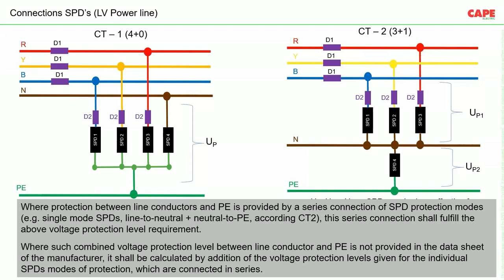A manufacturer should mention a combined voltage protection level in their datasheet. If not, it should be calculated by adding the voltage protection levels of the individual SPD modes connected in series — that is, voltage drop across SPD1/2/3 plus voltage drop across SPD4, along with the voltage drop across the connecting wires.